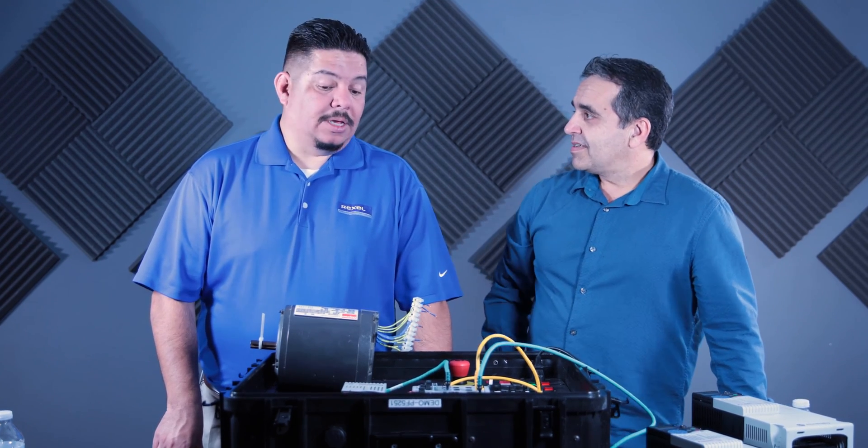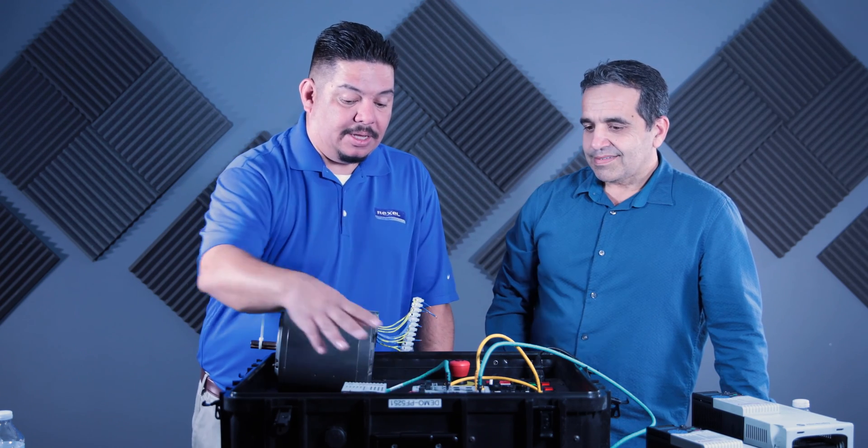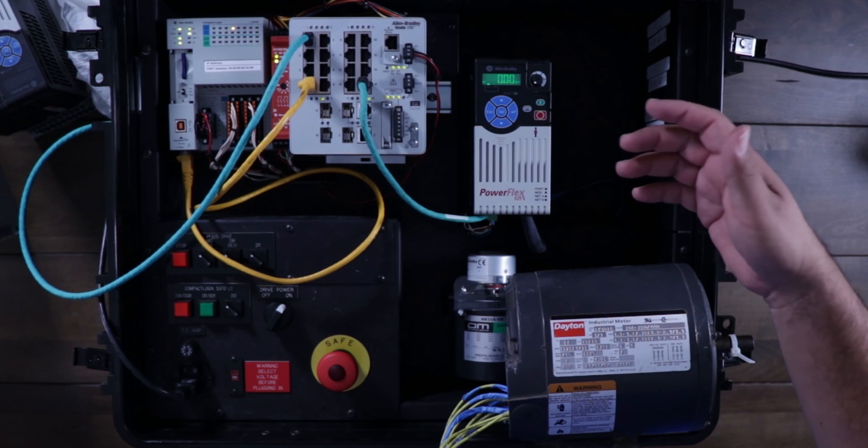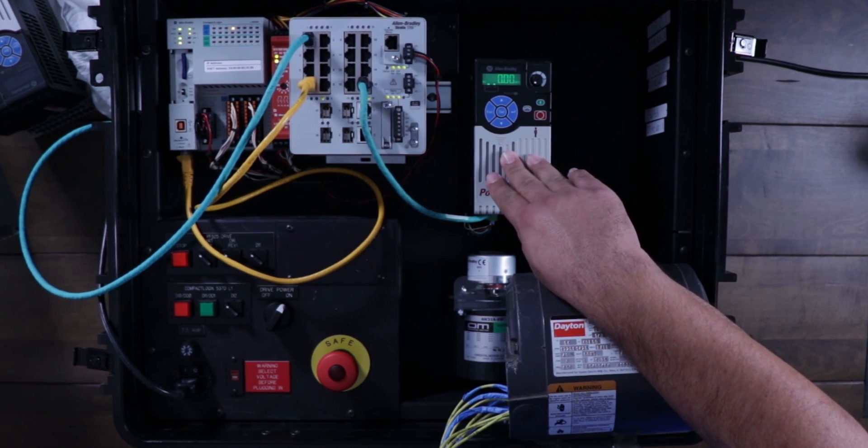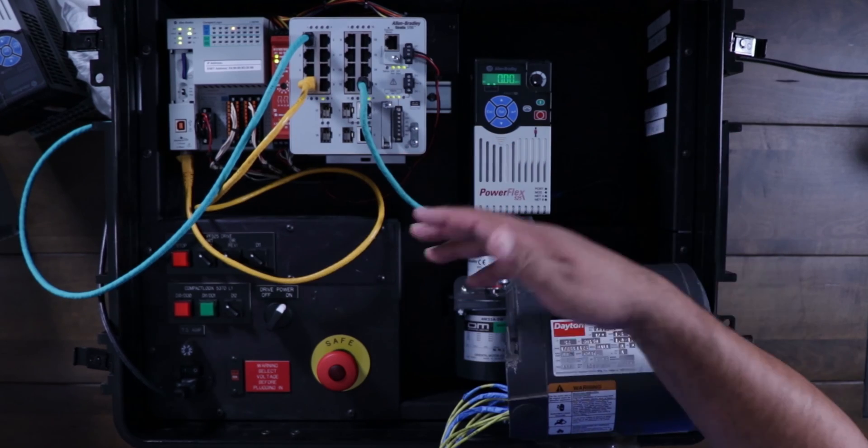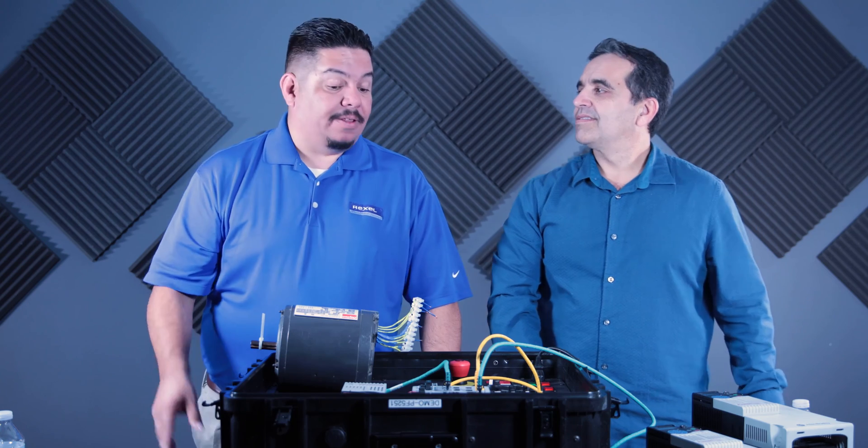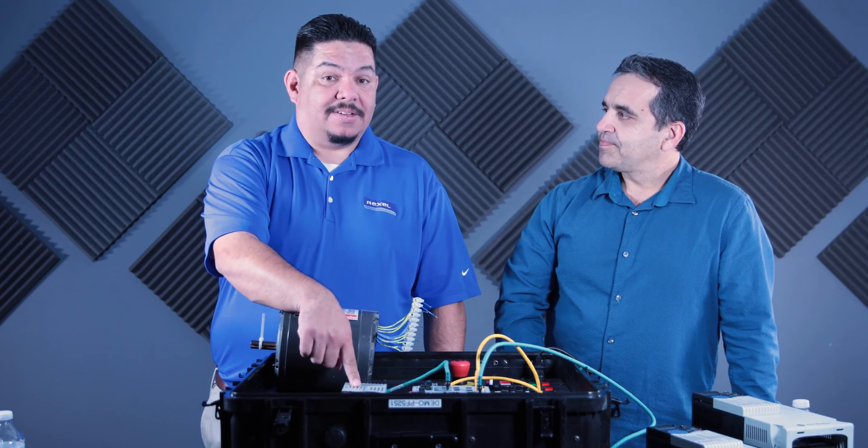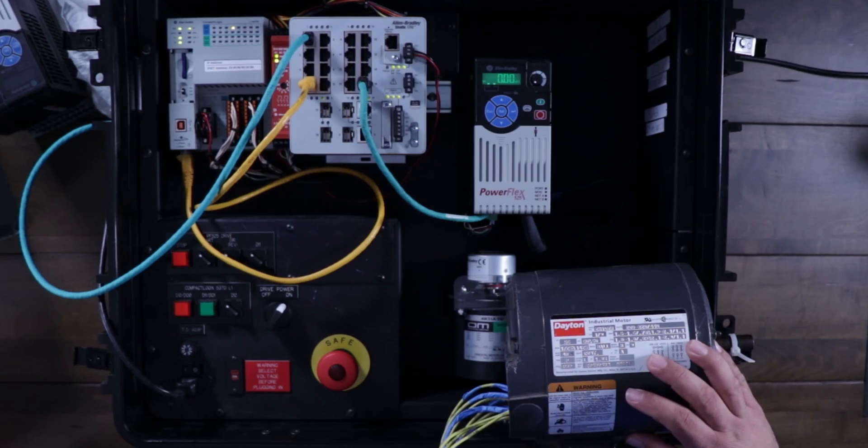So basically this drive is ready to go. It is. The other thing we need to probably talk about though, since we have a managed switch here is automatic device configuration. And what that allows is whenever this drive fails, if it fails, anybody, any maintenance person, anybody that you have authorized in your facility to change a drive out can do it without any prior knowledge of the parameters or settings, or even knowledge of a PLC. All they have to do is put in a new drive and the automatic device configuration will take over completely.